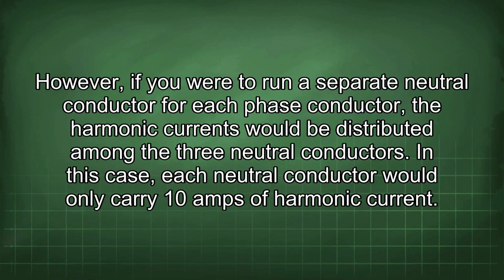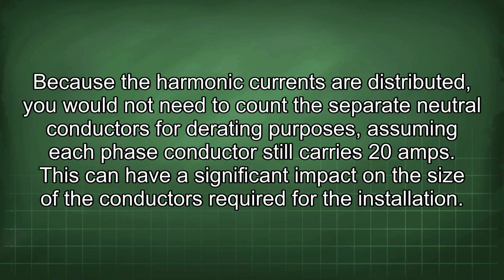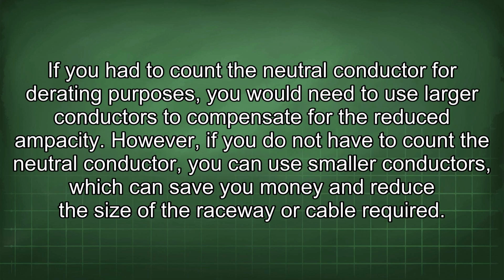However, if you were to run a separate neutral conductor for each phase conductor, the harmonic currents would be distributed among the three neutral conductors. In this case, each neutral conductor would only carry 10 amps of harmonic current. Because the harmonic currents are distributed, you would not need to count the separate neutral conductors for derating purposes, assuming each phase conductor still carries 20 amps. This can have a significant impact on the size of the conductors required for the installation. If you had to count the neutral conductor for derating purposes, you would need to use larger conductors to compensate for the reduced ampacity. However, if you do not have to count the neutral conductor, you can use smaller conductors, which can save you money and reduce the size of the raceway or cable required.